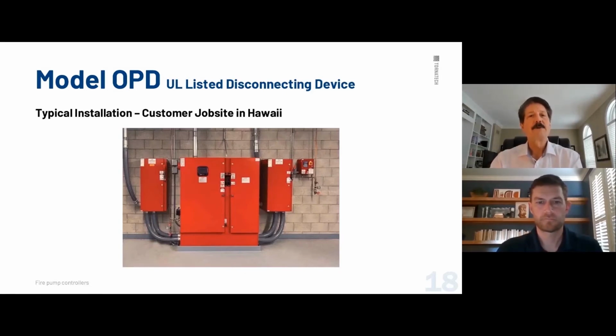Now, there is a typical install. I showed you a schematic picture, block diagram. This is a real install. And it's a job site in Hawaii. Obviously, you can see normal power here, emergency power here, normal power transfer side. This was sent in by one of our customers. This is a really beautiful install. And the unfortunate circumstance, and Cole and I were just talking about this, is one we missed out on. We were not able to make the trip to do a commissioning on this. They did it on their own, unfortunately.